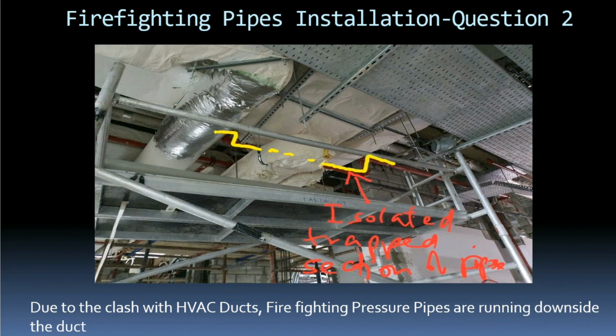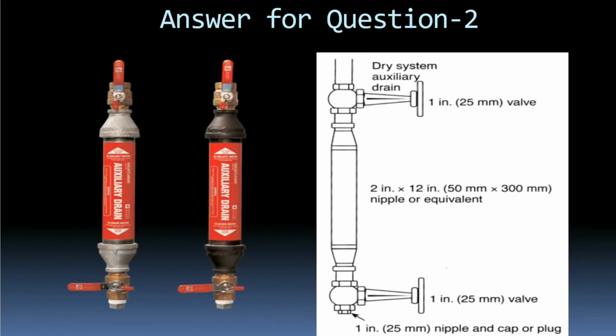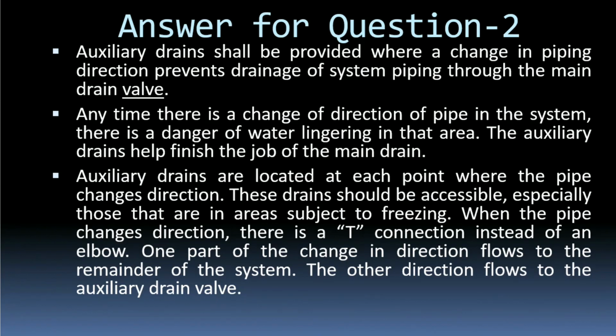So the answer for this question is, first, it is not acceptable to make a pipe go up and down like this. Second, you might have seen this arrangement, the auxiliary drain. The auxiliary drain shall be provided where a change in piping direction prevents drainage of the system. Normally if you make an up and down, the water will gather in that particular space, and we cannot drain the water from it. That is the reason we use this component, the auxiliary drain.